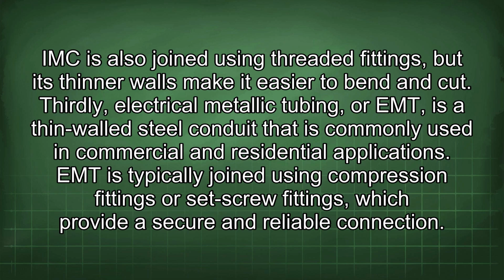IMC is also joined using threaded fittings, but its thinner walls make it easier to bend and cut. Thirdly, electrical metallic tubing, or EMT, is a thin-walled steel conduit that is commonly used in commercial and residential applications. EMT is typically joined using compression fittings or set screw fittings, which provide a secure and reliable connection.